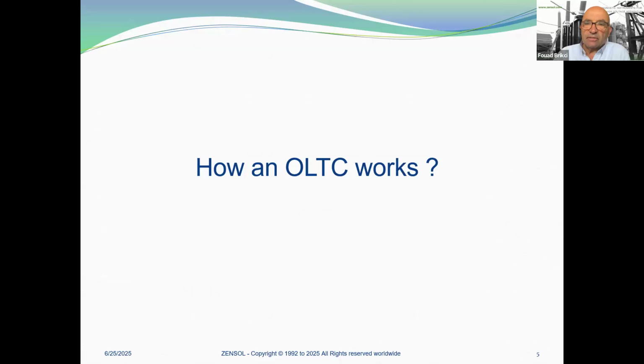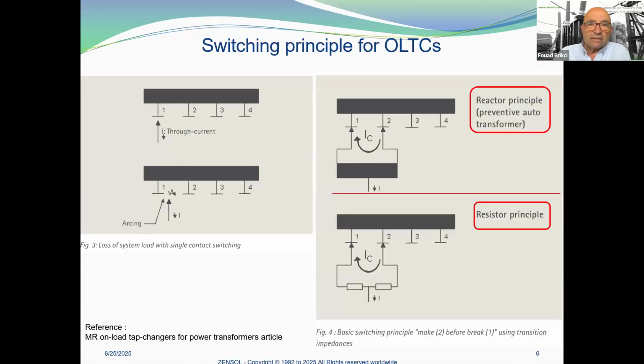So how does an OLTC work? In fact, we need to move from tap 1 to tap 2. On the left picture, you can see we have to move from tap 1 to tap 2. How to do it? On the left picture, simply changing taps during an energized status is unacceptable due to momentary loss of system load during the switching operation. On the right picture, the make-before-break contact concept shown in figure 4 is therefore the basic design for all OLTCs. And the transition impedance, in the form of a resistor or a reactor, consists of one or more units that bridge adjacent taps.